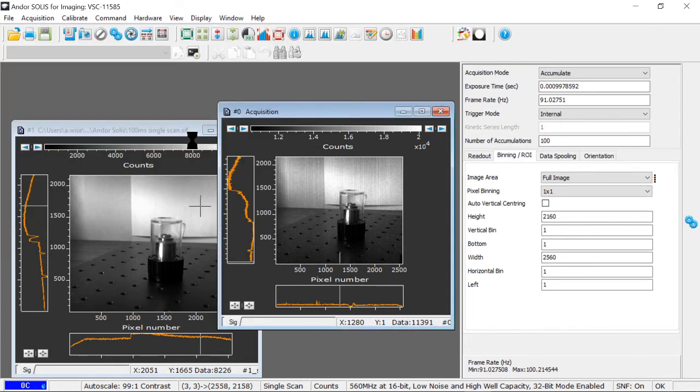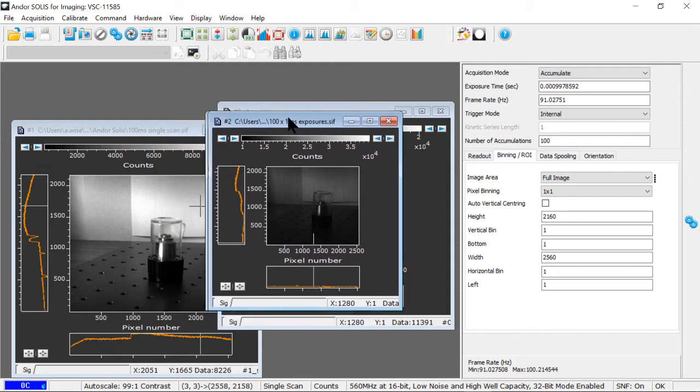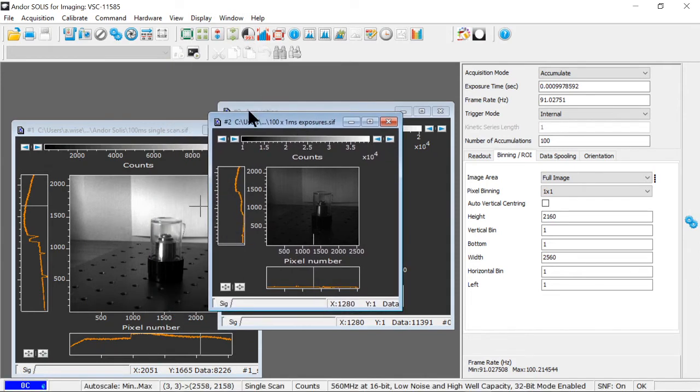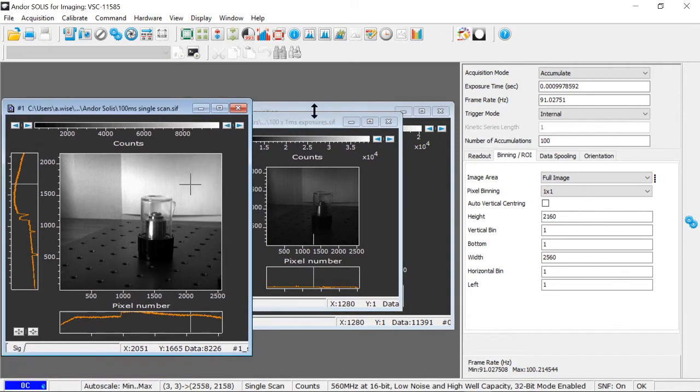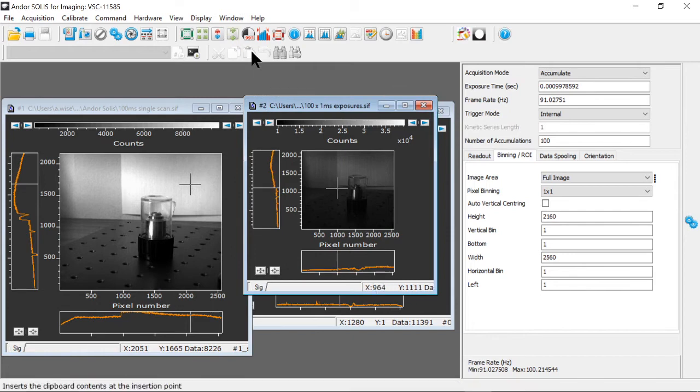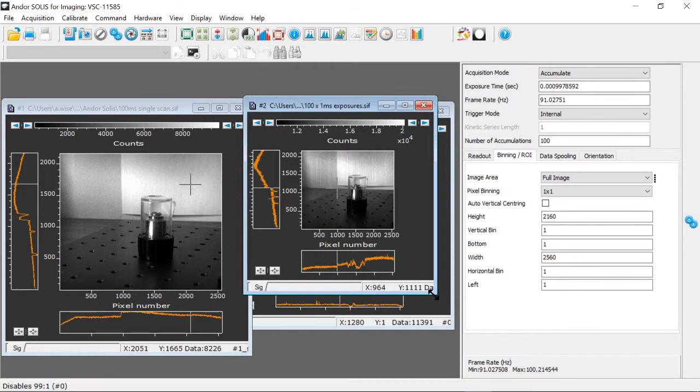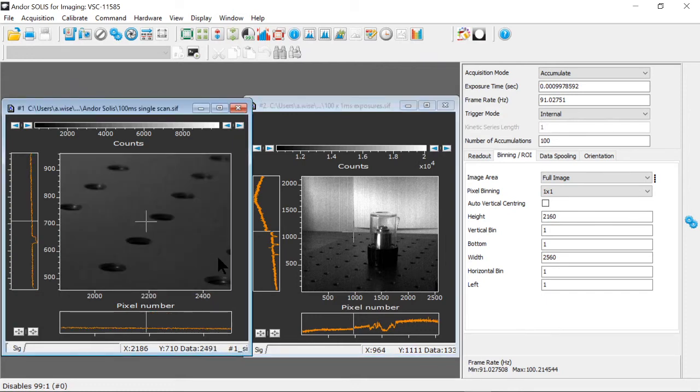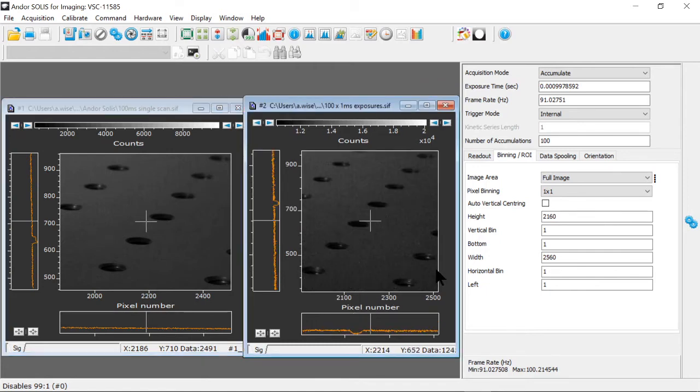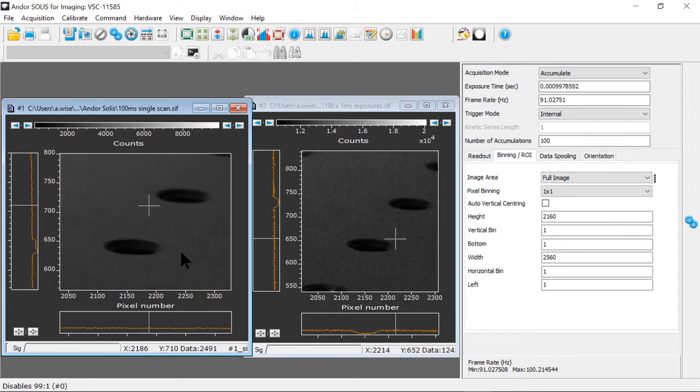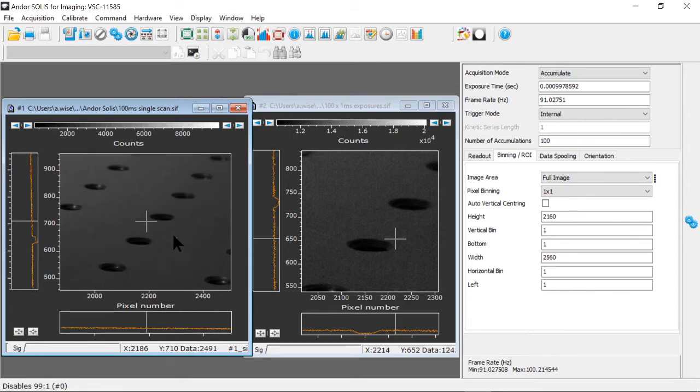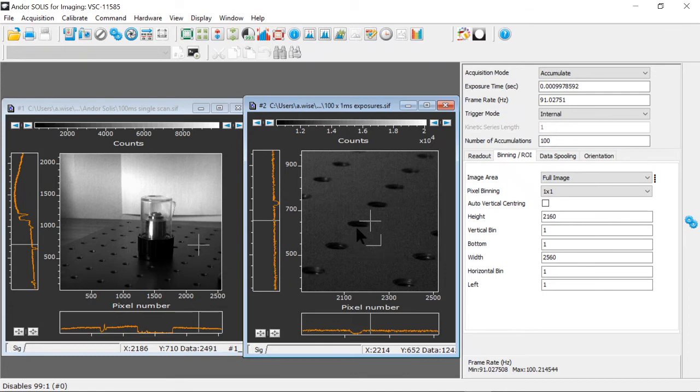So you can see right off the bat there's quite a bit more noise in this accumulated image, although it has the same total amount of signal captured. And I'll set them up to have the same contrast. So you can probably see right off the bat, but if I zoom in on someplace, say here and here, you can see I've added, through the accumulation process, quite a bit more read noise, which shows up as grain in the image. And maybe I'll zoom in a little bit more to see if that might be obvious. I hope this isn't taken away by video compression when I post it, but I think that even in the unzoomed image you can see it.